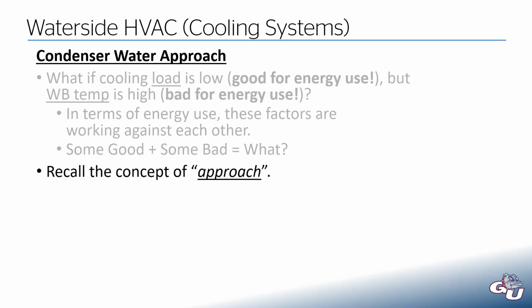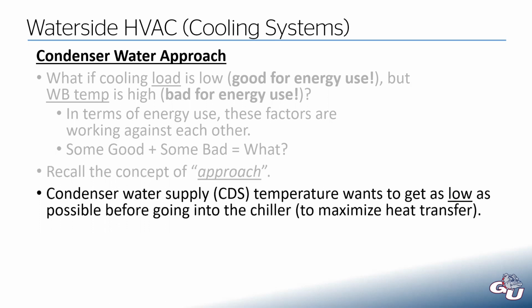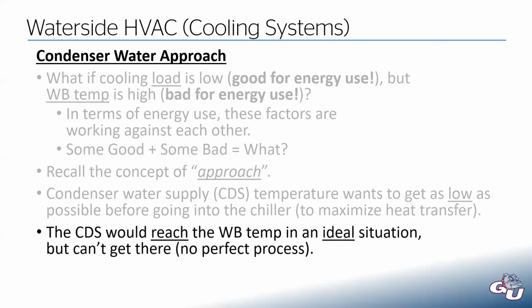So that brings us a long way around back to this idea of approach. So the condenser water supply wants to get as low as possible before going into our chiller, because the lower we can drive that temperature, that's going to maximize our heat transfer. If our condenser water supply into the chiller is low, that makes it easier for the chiller to move heat from the chilled water stream to the condenser water stream. The supply would reach the wet bulb temperature in an ideal situation. So if our wet bulb temperature is 65 degrees Fahrenheit, ideally, in a perfect world, the condenser supply could also get down to 65, but it couldn't ever get any lower. But in the real world, that's not what happens. We can't quite get there.